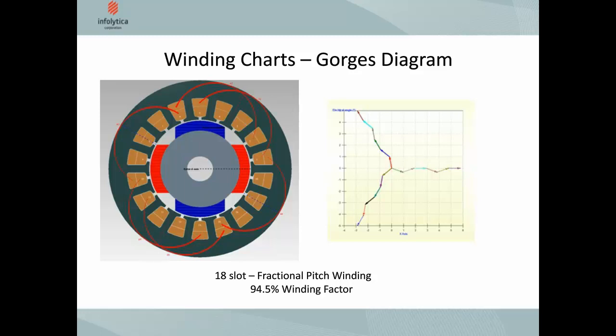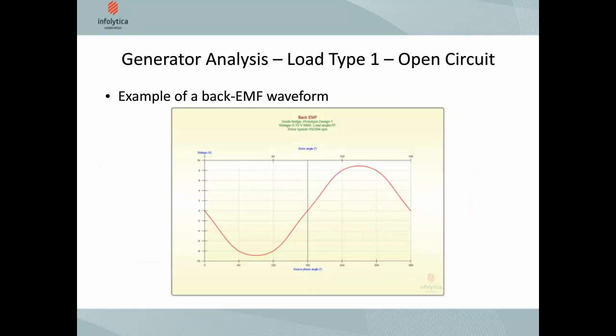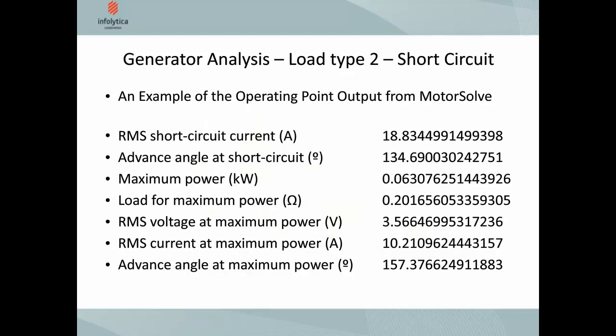Now we go on to generator analysis. The first thing to look at is the back EMF waveform — this is the open circuit load type. The maximum of that back EMF determines the maximum power and voltage we can output from our generator. Here is an example of the short circuit analysis showing quantities such as short circuit current, advance angle at short circuit, maximum power for the machine, and various other quantities useful for characterizing your generator.